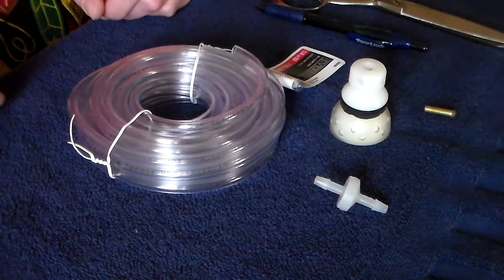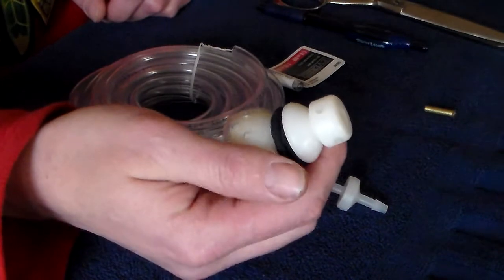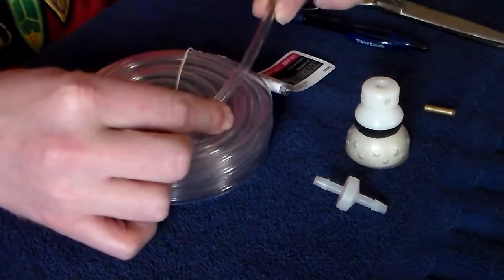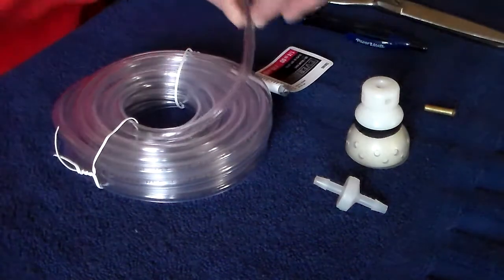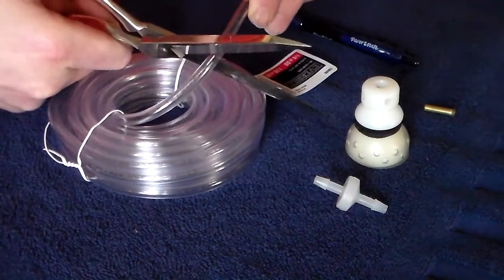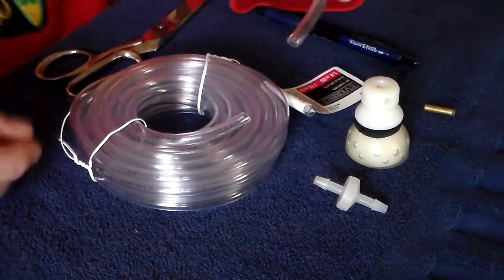What I do is you take your DTR bell with your gripper installed. You'll take a piece of quarter-inch vinyl tubing and cut it approximately 2.5 inches in length.